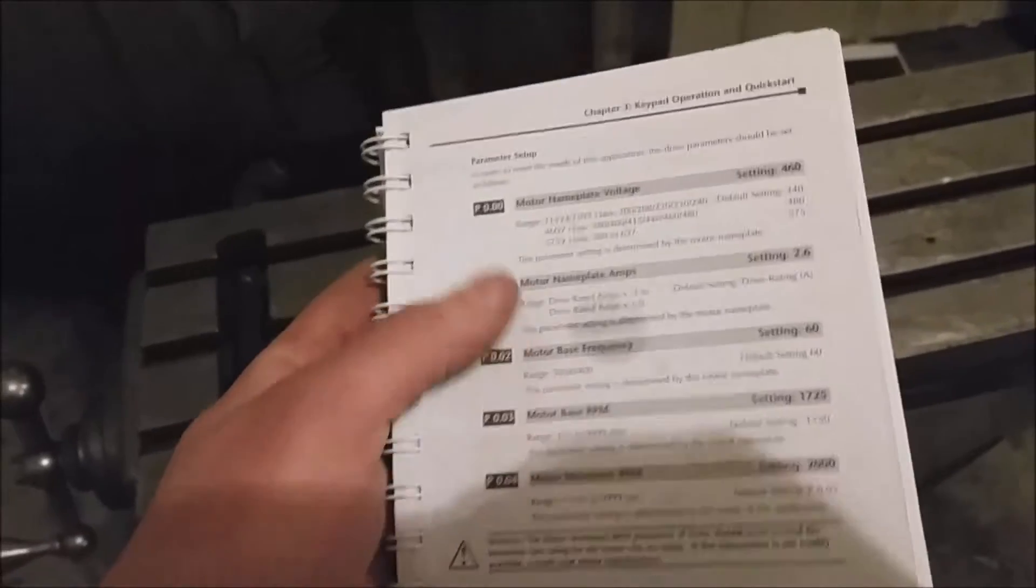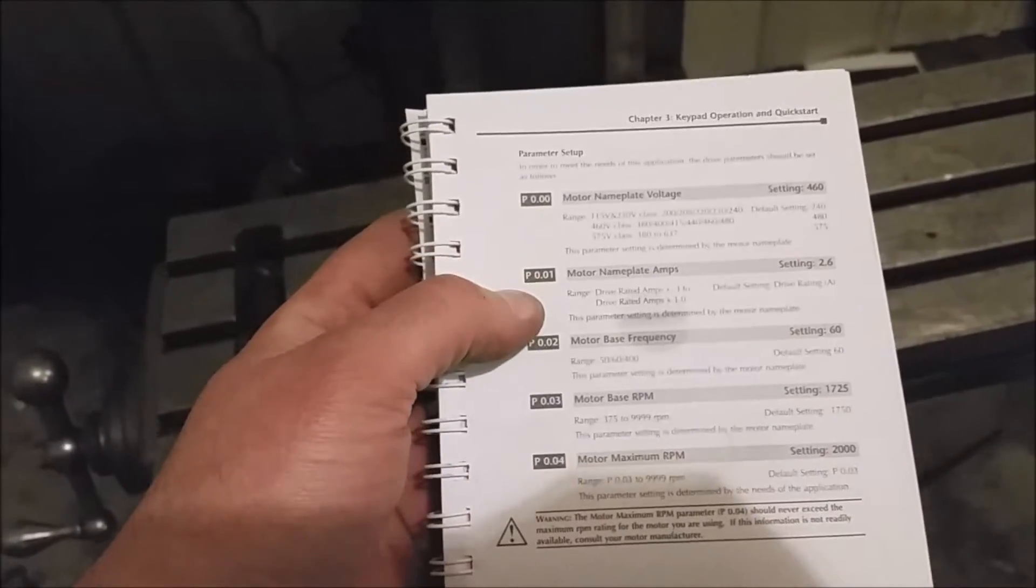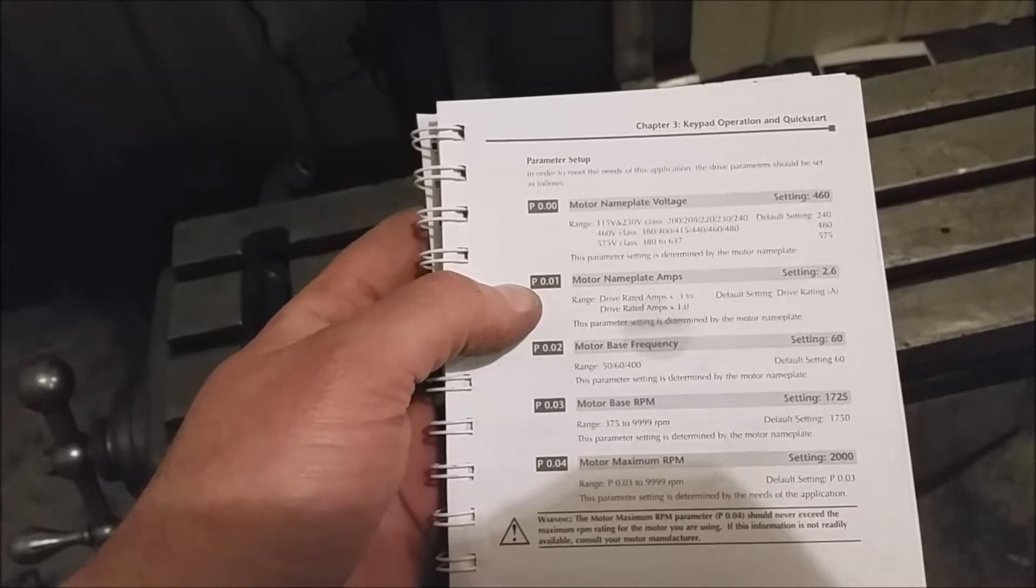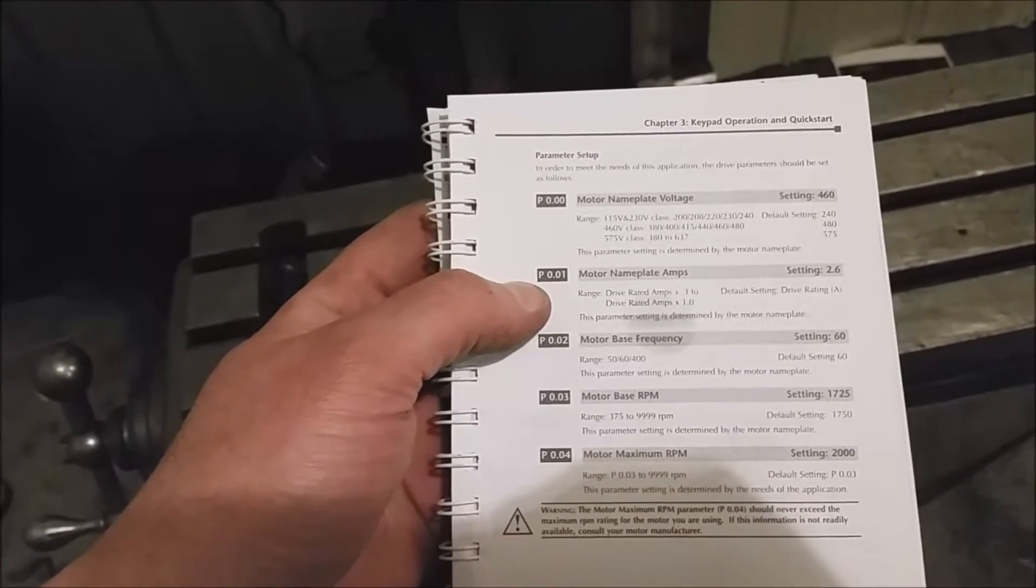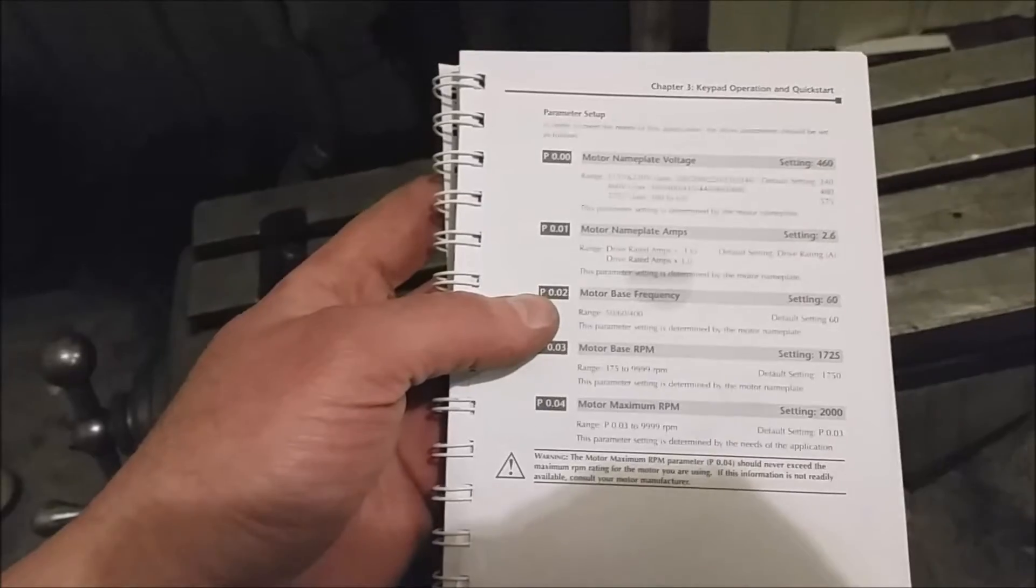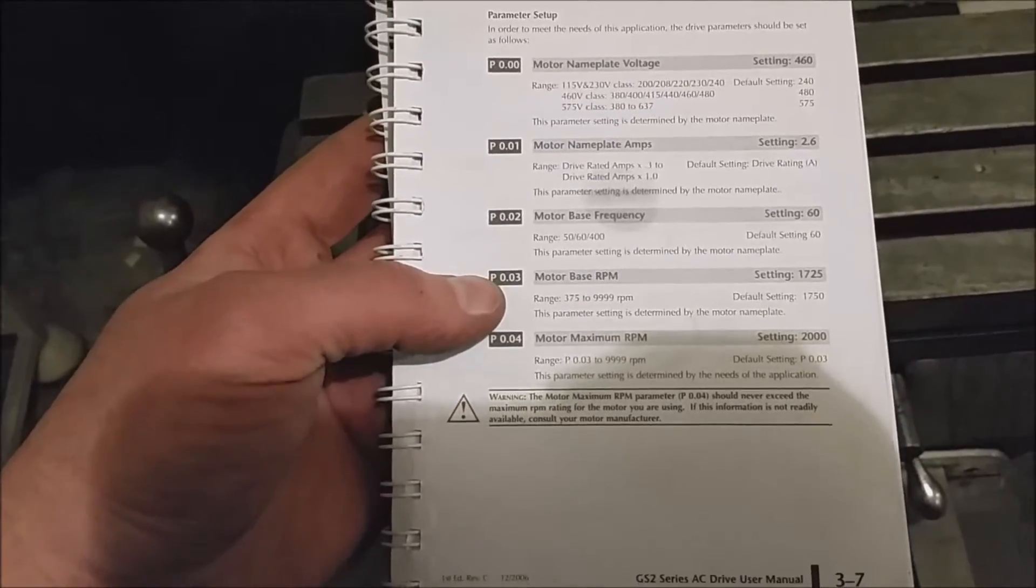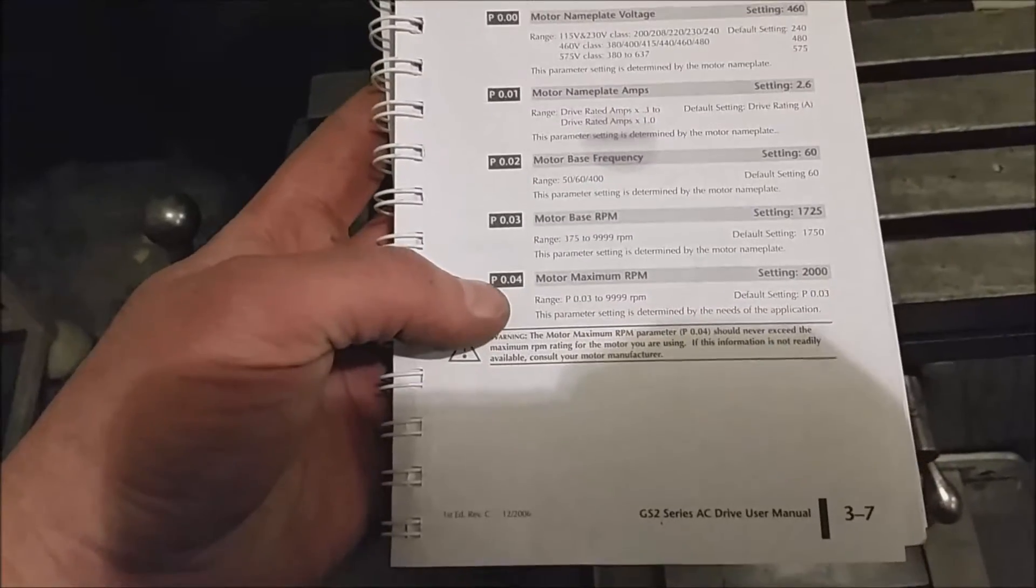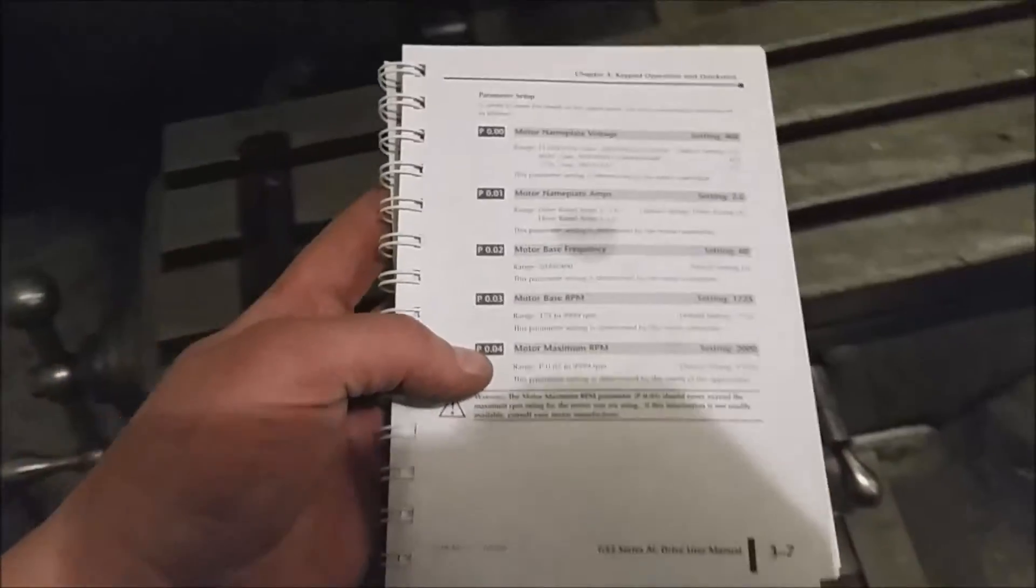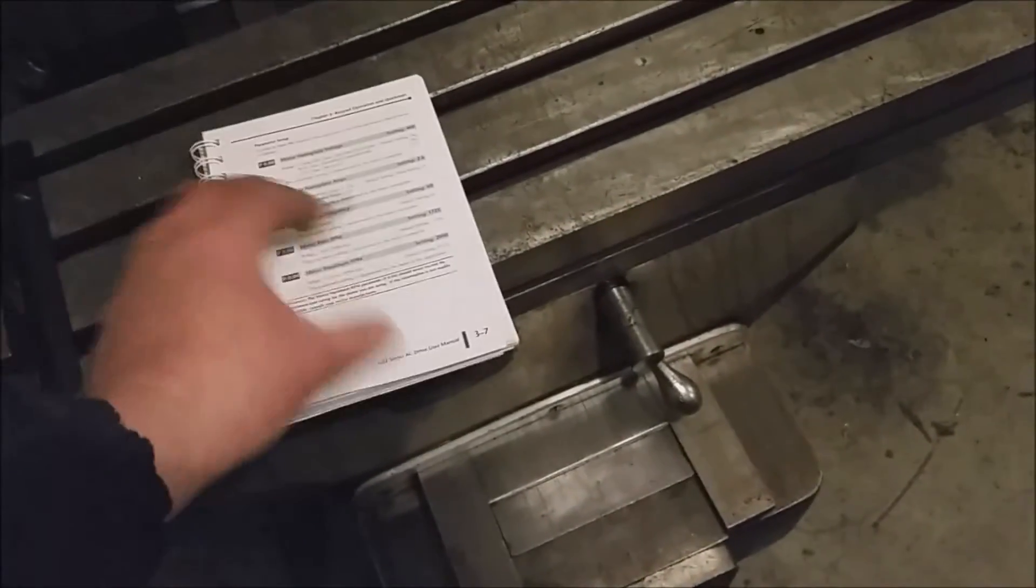What you've got to do to start with is really simple. The manual is really simple the way it shows you. You hit your program key and you basically just start walking down through each one of these things: your nameplate voltage, your motor nameplate amp, your base motor frequency, which in my case is 60 hertz, your motor base RPM, and your motor maximum RPM.